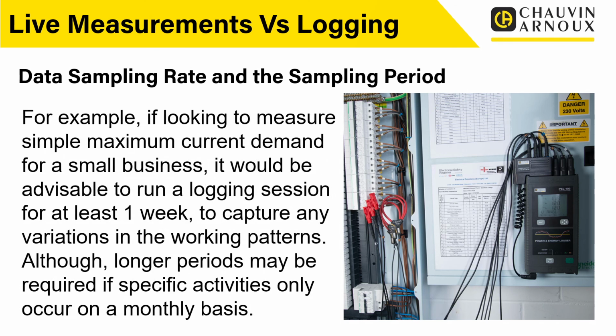For example, if you're looking to measure simple maximum current demand for a small business, it would be advisable to run the logging session for at least a week to capture any variations in working patterns, although longer periods may be required if specific activities only occur on a monthly basis. So it's important to talk to the customer, to understand what you're measuring and any variations, and then allow for that within your measurements.